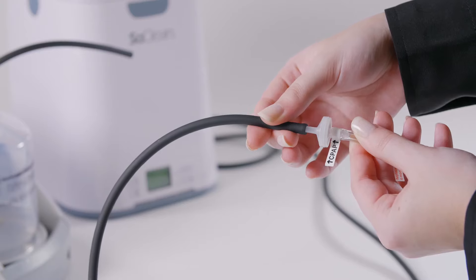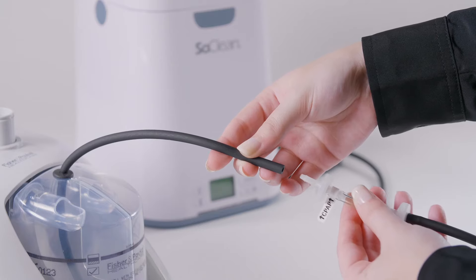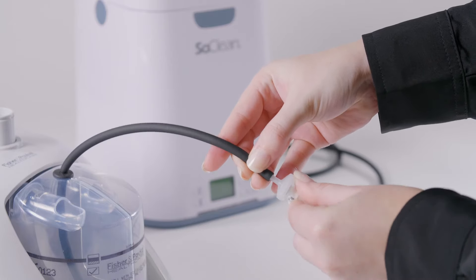Remove the piece of injection hose that is attached to the CPAP end of the check valve. Connect the adapter's injection hose to the check valve on the main SoClean hose.